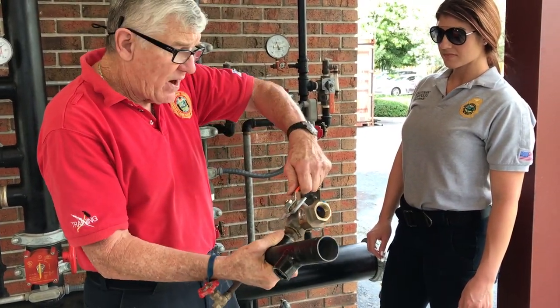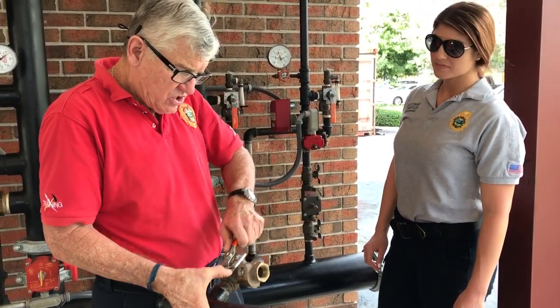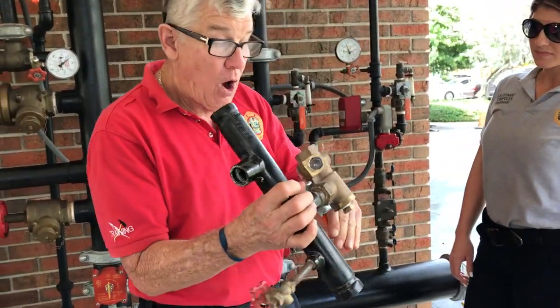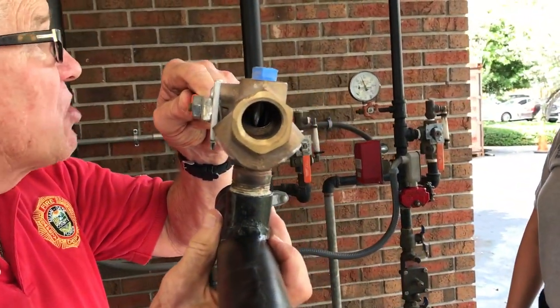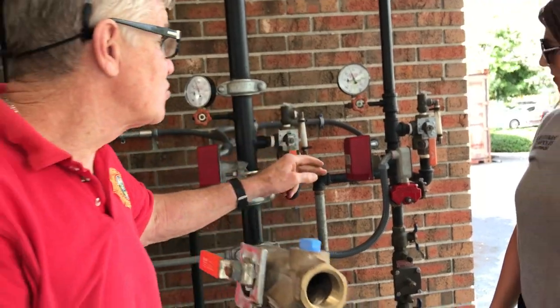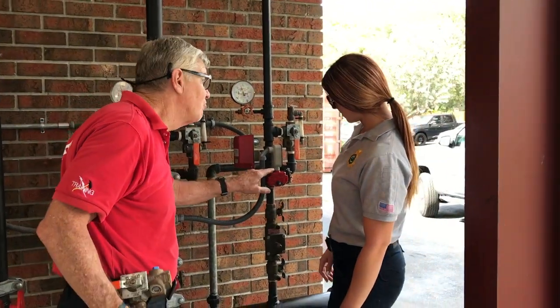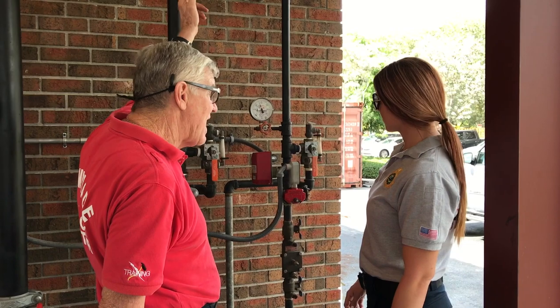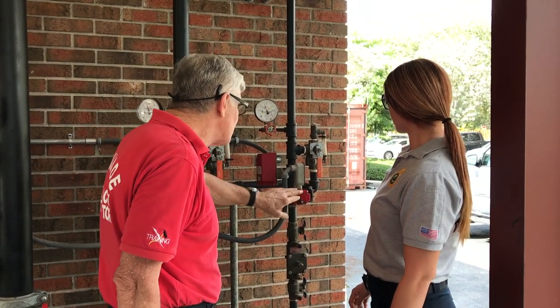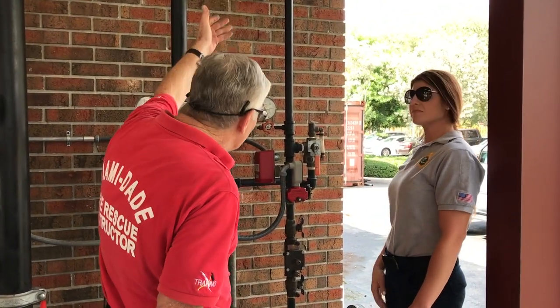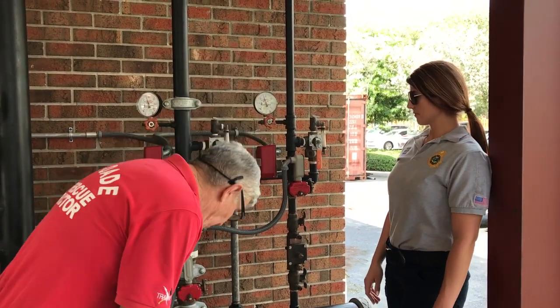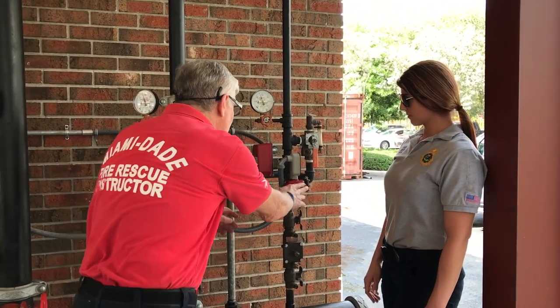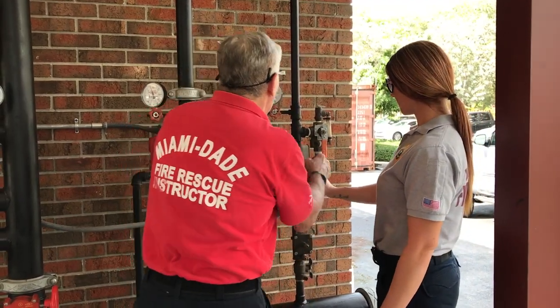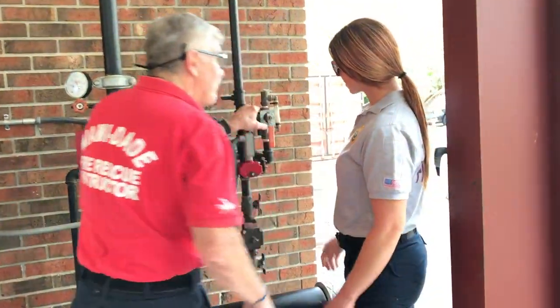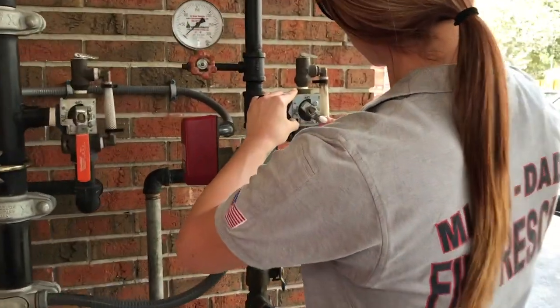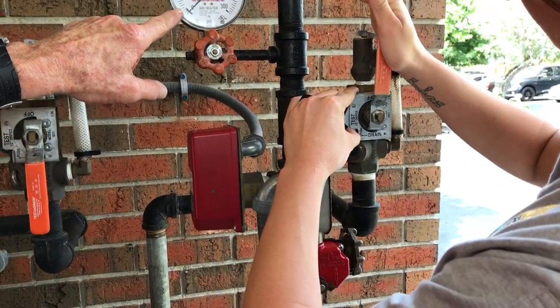Tammy, we're gonna go all the way to drain, which in this case will present a full 1-inch drain to drain the water that is gonna be trapped between the closed valve and the sprinkler head that has been activated. Otherwise, if you just close the valve, the water will continue to run. So we're going to shut down the control valve, we did. Now, just lift this up and move that valve to drain. There you go, and you see we've lost the pressure, we've drained it.